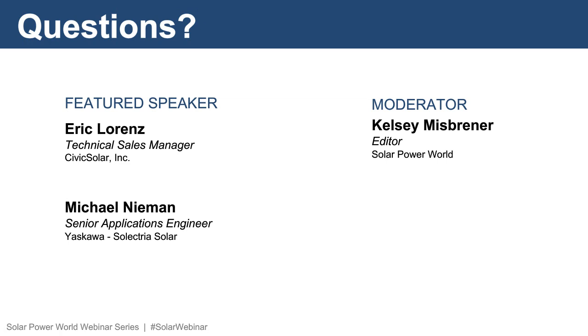I can take this one. Functional grounding refers to a connection to ground that is not solidly grounded. Traditionally in PV systems, the connection to ground has been through a fuse or overcurrent device to meet the requirements of 690.5 ground fault protection. In doing so, the systems were not solidly grounded. They were functionally grounded.